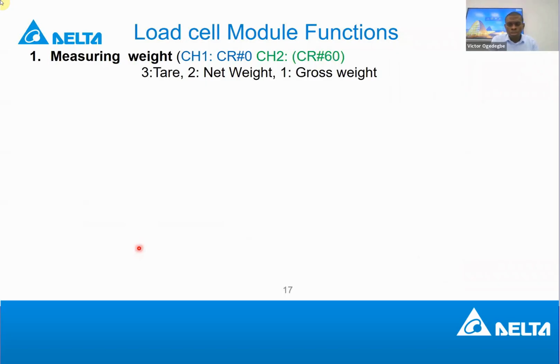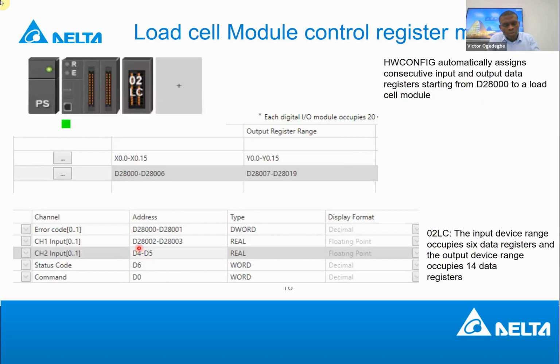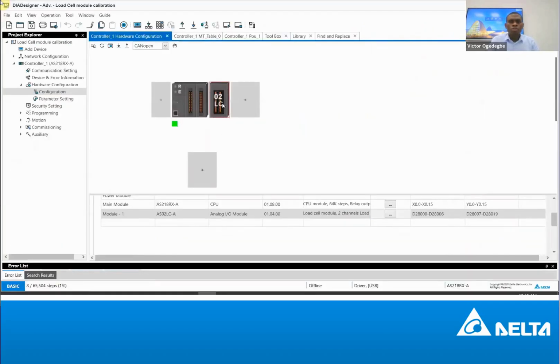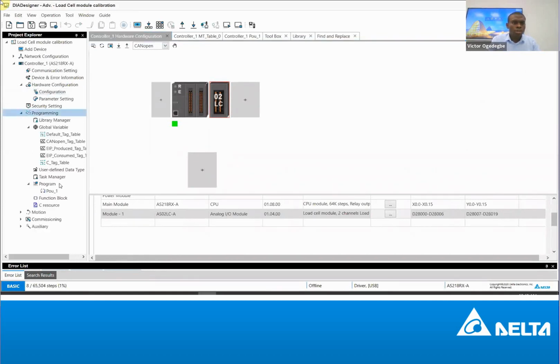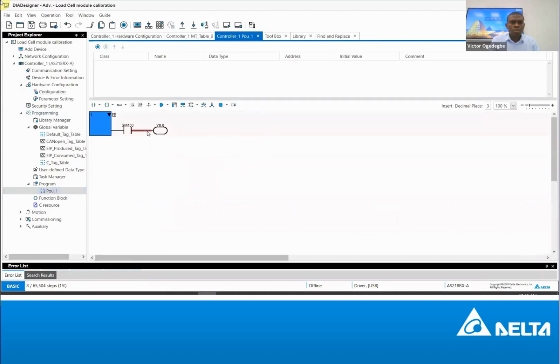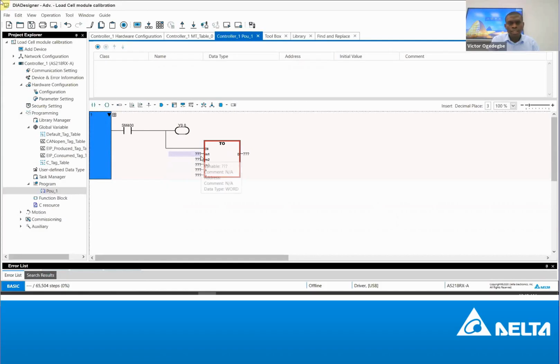Okay, before we go to the function, let's just play around a little bit with the interface I showed us earlier. If you want to configure the module, it's two things, like I told you, TO instruction. If you come to programming, for example, if you write TO here, you see this is the TO instruction. The operand of this TO instruction is here: you specify the address in the module you want to write to, then the data you are sending goes directly to the control register that you're writing to.